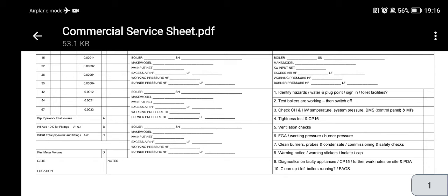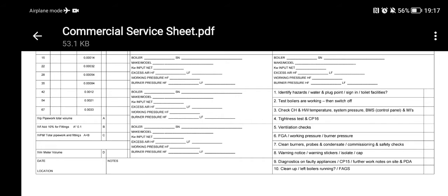Step seven: strip a boiler down and clean it if you have the gaskets. For atmospheric boilers you can clean them down, brush them through, clean the ignition and detection probes with a file or replace them, and check spark distances. You can also clean the condensate trap if it's a condensing boiler, replenish the water, and carry out commissioning and safety checks required for service. If a boiler isn't working well, issue a warning notice, put a warning sticker on, and isolate or cap if necessary. Then move on to the next boiler and repeat steps six and seven.